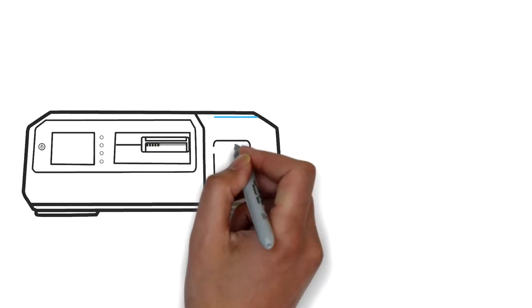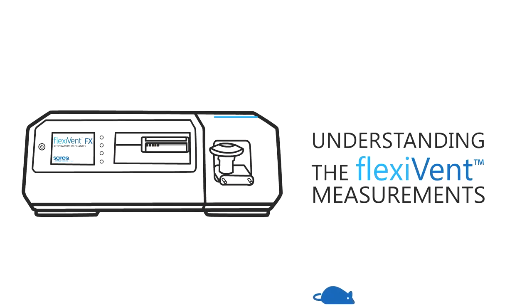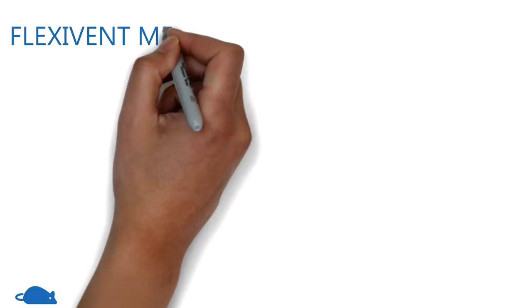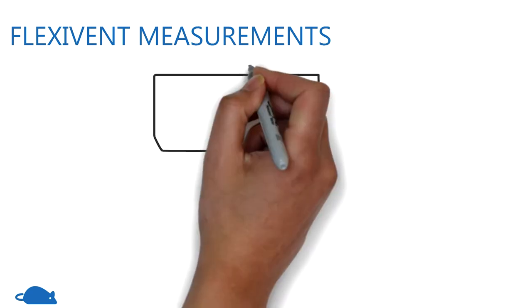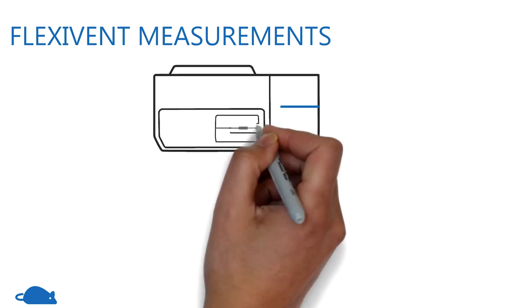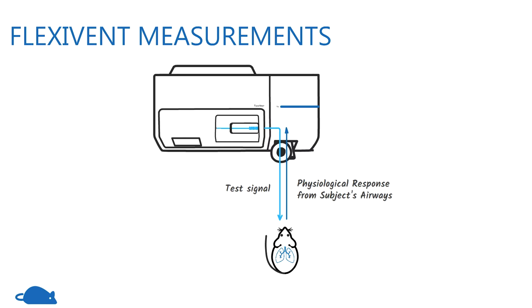The following video will provide a brief overview of the flexi-vent manoeuvres and outcomes. The flexi-vent uses an active measurement technique. Using this technique, test signals are introduced to the subject's airways, and through changes in pressure, volume, and flow, the mechanical properties of the respiratory system can be measured.